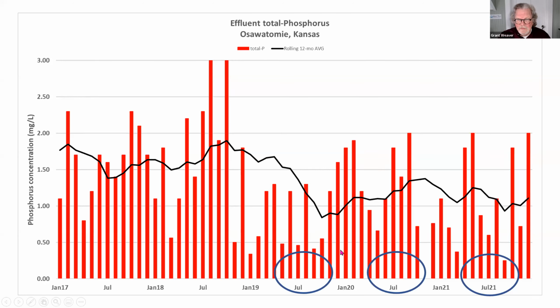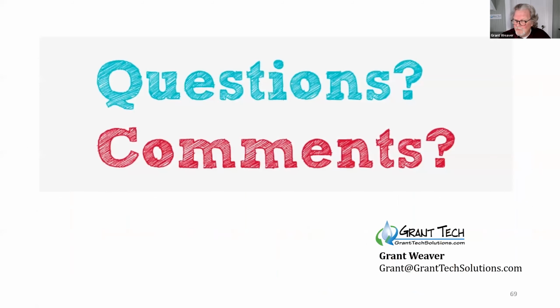What I do want to point out is that the summer months, if you compare these summer months to the previous 2 summer months, you can see that once this effort was started, notwithstanding the periodic plugging of the pumps and the fact that he couldn't do it in the winter, it seemed to have really ratcheted things down. So I'm going to hang on to that. We're going to keep working with SBRs, and we're going to find a way, and maybe a year from now, 2 years from now, I can come back and share some really more exciting stories. Right now, it's more in the opportunities department.